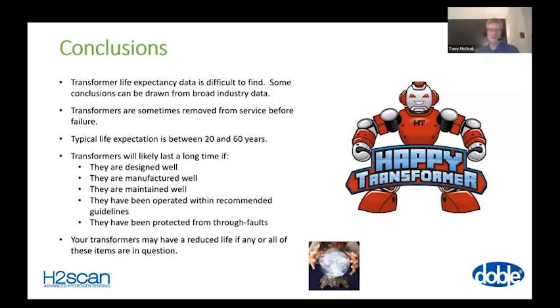Anything else to add? Yeah, if I may, just briefly, if you look at IEEE C57.143, it'll tell you what you might want to monitor on different parts of a transformer, but it won't give you limits as to what you should set. It's the same reason why we don't have common limits for tire pressures on a car. Different manufacturers' tires will have different limits. So you have to understand your own individual transformer application for bushing monitoring, for partial discharge monitoring, for temperature monitoring, for dissolved gases monitoring. And the data you generate from the monitor should help identify the most common failure modes.